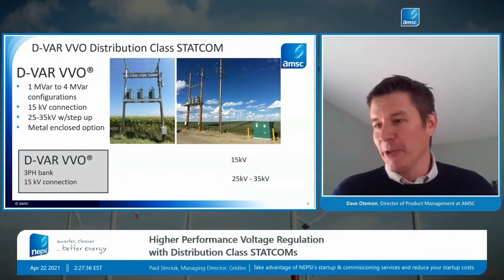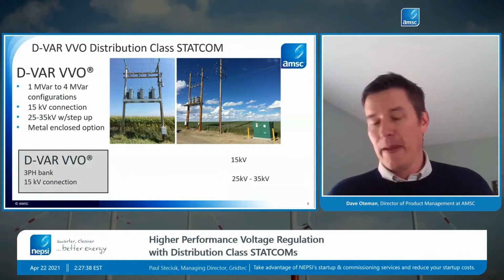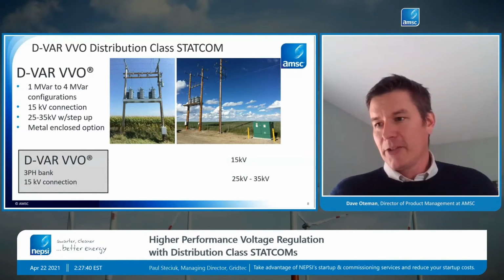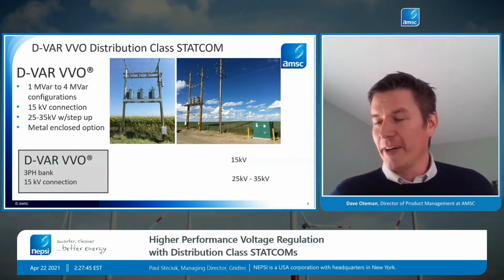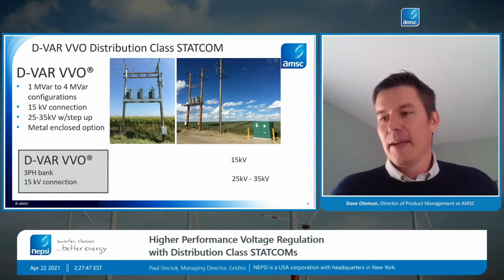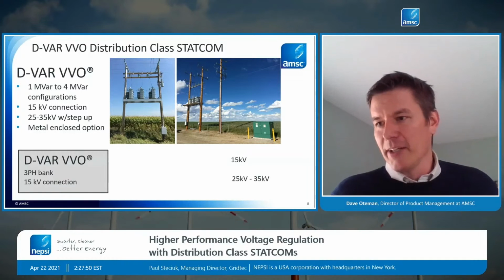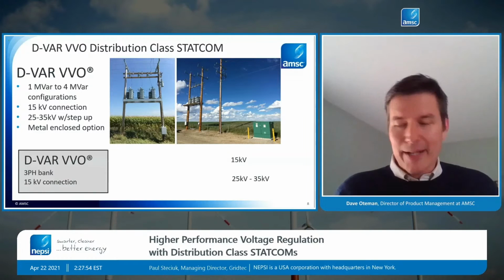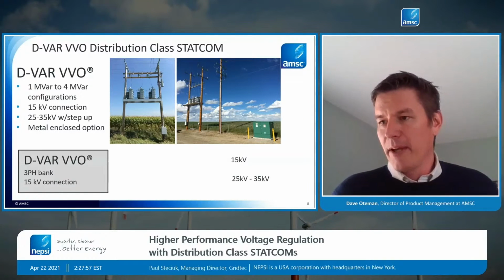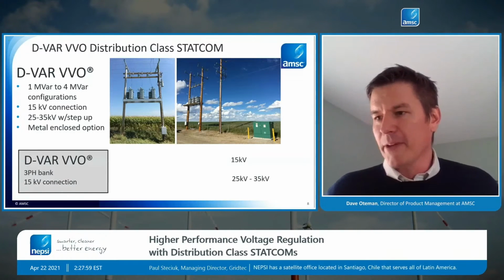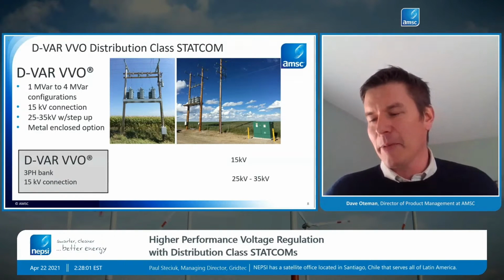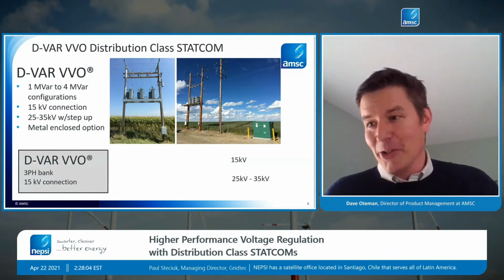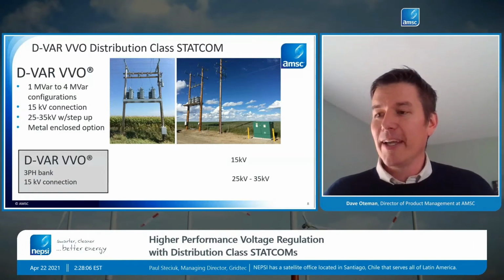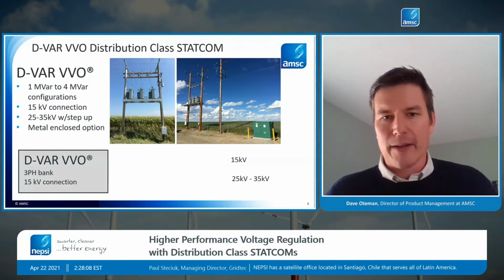I talked about distribution class equipment, and we know that historically transmission systems is where STATCOMs really got their start, and they're very mature and widely adopted. Bringing this technology into the distribution system requires a product that's engineered from the ground up to meet distribution requirements. You can't take a transmission STATCOM and just use part of it. It really has to be re-engineered, and that's what we did with the D-VAR VVO product line.